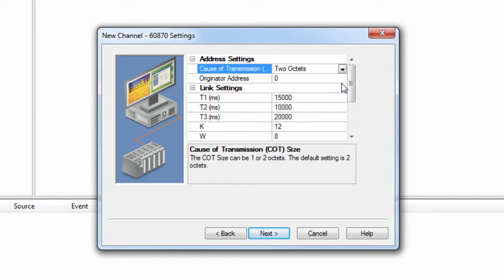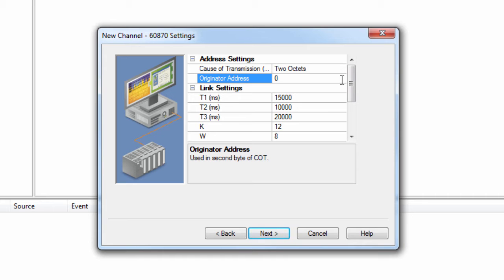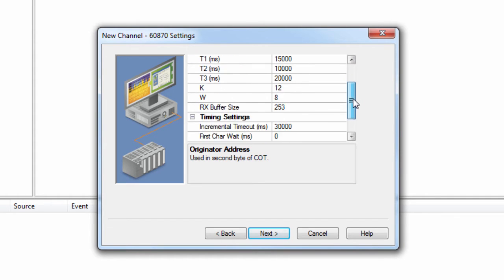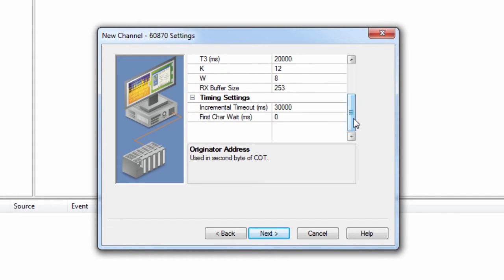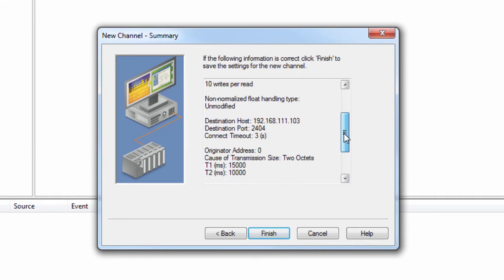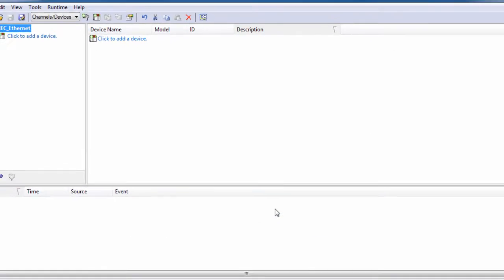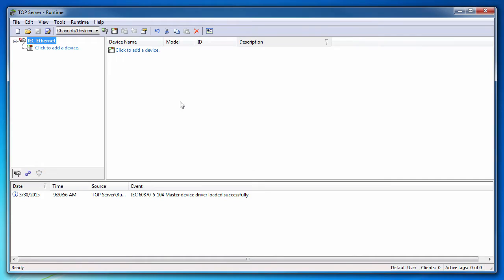The originator address is used by a dual-master device to route responses from a slave to the correct master. The valid range is 0 to 254. The default setting is 0. The remaining settings can usually be left at default. Click Next to review the channel configuration and choose Finish. You will now see your configured channel in the project.